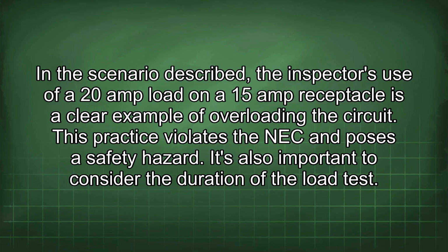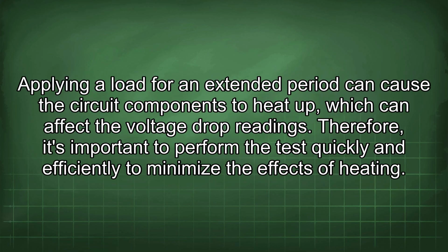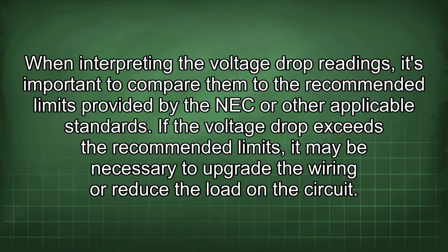In the scenario described, the inspector's use of a 20 amp load on a 15 amp receptacle is a clear example of overloading the circuit. This practice violates the NEC and poses a safety hazard. It's also important to consider the duration of the load test. Applying a load for an extended period can cause the circuit components to heat up, which can affect the voltage drop readings. Therefore, it's important to perform the test quickly and efficiently to minimize the effects of heating. When interpreting the voltage drop readings, it's important to compare them to the recommended limits provided by the NEC or other applicable standards. If the voltage drop exceeds the recommended limits, it may be necessary to upgrade the wiring or reduce the load in the circuit.